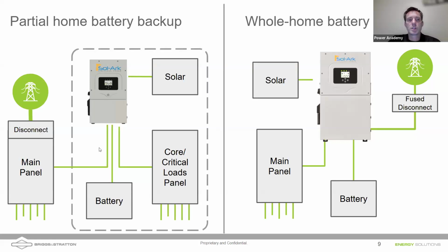And then in a grid down situation, that main panel would be isolated. So we're not using the Sol-Ark to send power back through the main panel onto the grid. And we'd have that battery providing power to power those core loads. And if you also have solar, that solar will stay on in a grid outage, be able to charge that battery up and be able to power those loads.